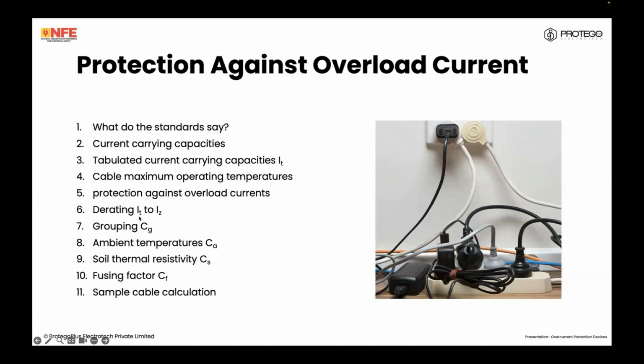How we derate IT, which is a tabulated value, to IZ, which is a current carrying capacity in the continuous service. We look at ambient temperatures, how these derate. If you have a higher ambient temperature, the current carrying capacity is reduced. Grouping, if you have many circuits grouped together, how the current carrying capacity is reduced. What the soil thermal resistivity is. If you have a cable buried in the ground, the ability of the cable to dissipate heat is affected. Fusing factor, which comes into conventional tripping times. This is what I'll focus on today.